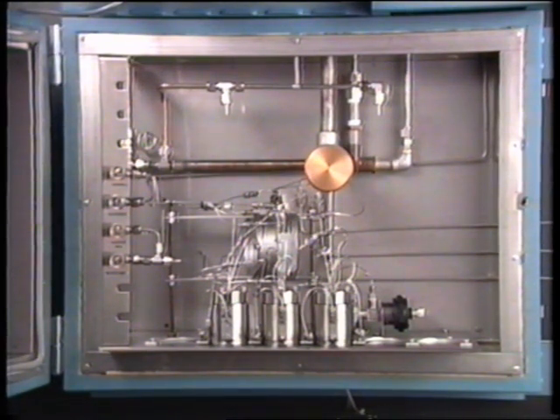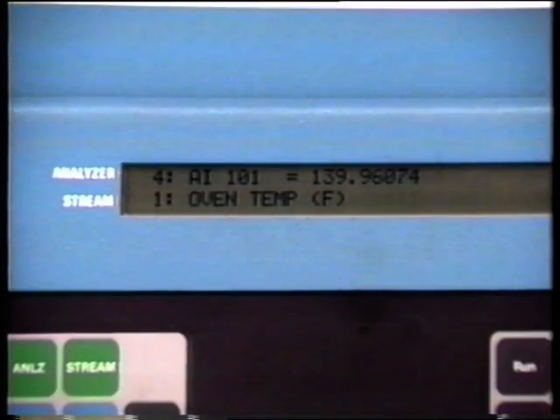Gas chromatographs require strict temperature control. As a result, the sample injection valve, column, and detector are housed in a thermal enclosure called the oven. Oven operations can take place at a wide range of temperatures, since consistency is the purpose of temperature control. Operating temperature can be as low as 10 and as high as 225 degrees Celsius, but it should remain constant.